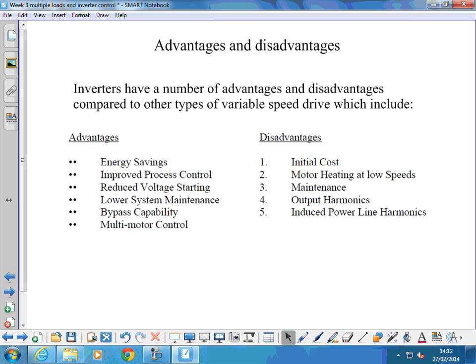lower system maintenance. They've got a reasonable bypass capability in most cases, so we'll look at that more deeply, but you can have a normal type starter bypassing the inverter if you need some kind of backup to get it running quickly if the inverter's broken down or similar. And some types will allow you to control multiple motors from the same inverter.